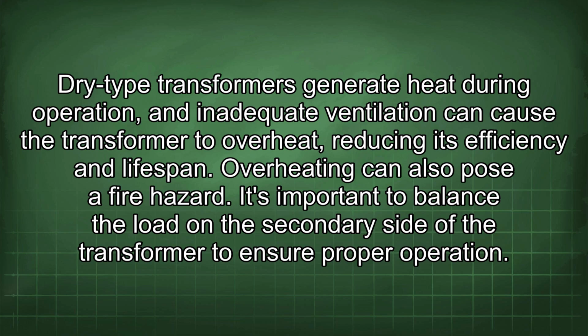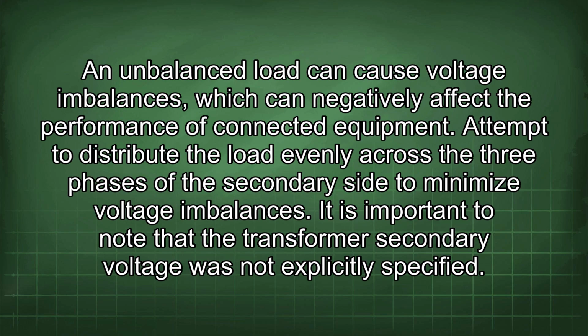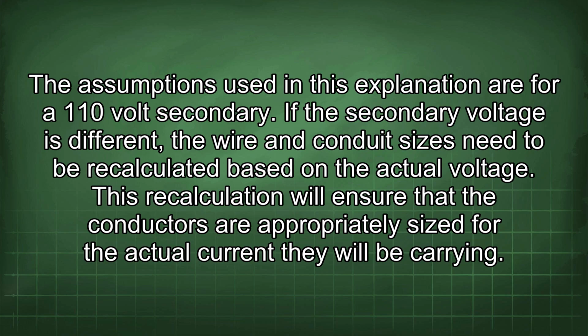It's important to balance the load in the secondary side of the transformer to ensure proper operation. An unbalanced load can cause voltage imbalances, which can negatively affect the performance of connected equipment. Attempt to distribute the load evenly across the 3 phases of the secondary side to minimize voltage imbalances. It is important to note that the transformer secondary voltage was not explicitly specified. The assumptions used in this explanation are for a 110 volt secondary. If the secondary voltage is different, the wire and conduit sizes need to be recalculated based on the actual voltage. This recalculation will ensure that the conductors are appropriately sized for the actual current they will be carrying.